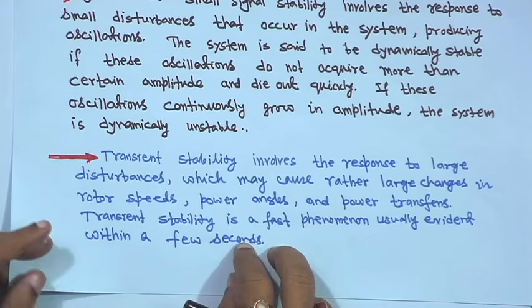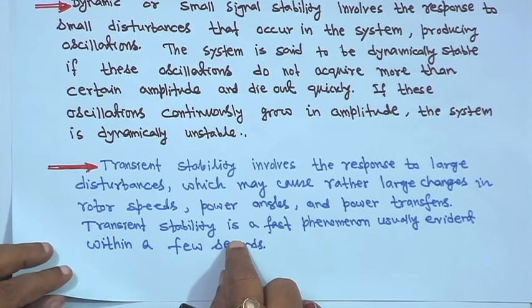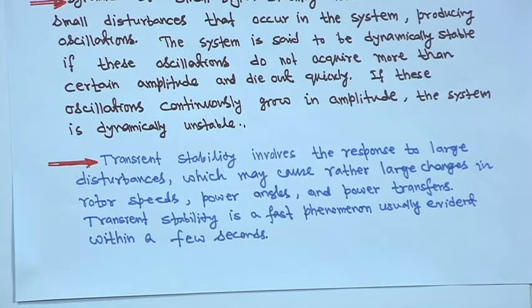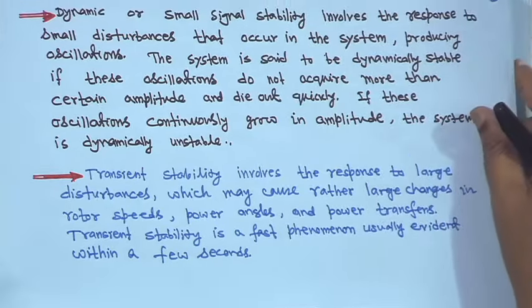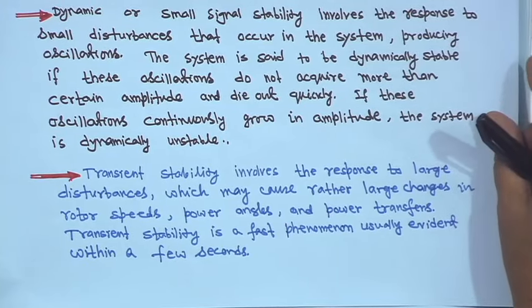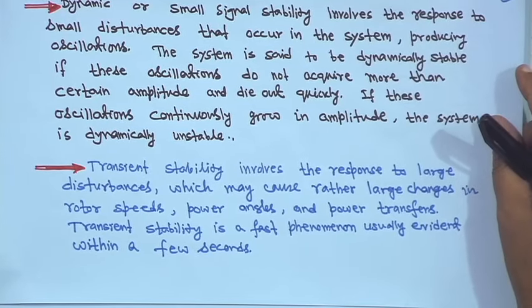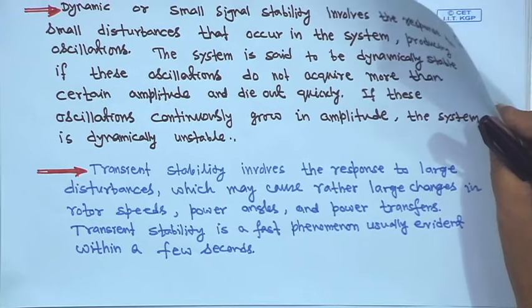Transient stability is basically within a few seconds. When such a fault occurs, it has to be cleared very quickly — it may be four cycles or six cycles. These are the three different types of stability: steady state stability, small signal or dynamic stability, and transient stability. Our concern for this course will be transient stability, and generally the single machine infinite bus system.